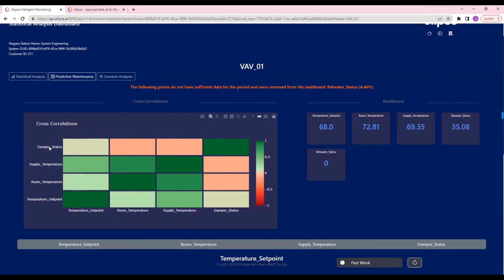We show cross correlations, so you can see, for example, as the damper position goes up, there's not a strong connection to the temperature going up. The room temperature actually goes down, and supply temperature is going down.